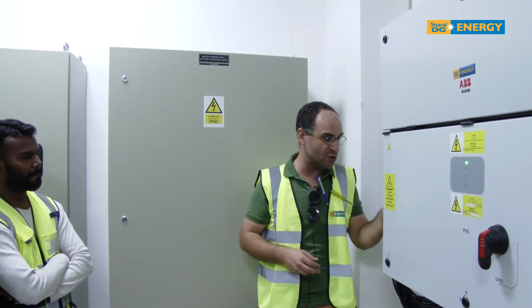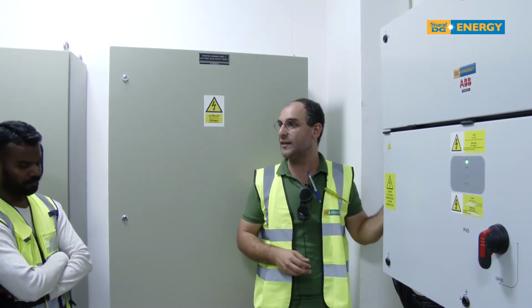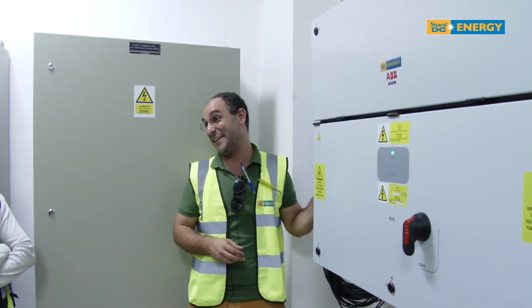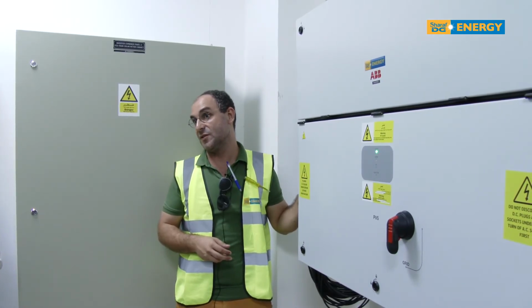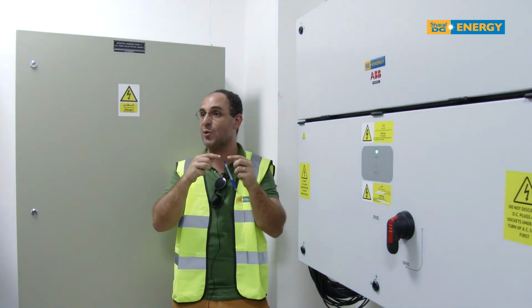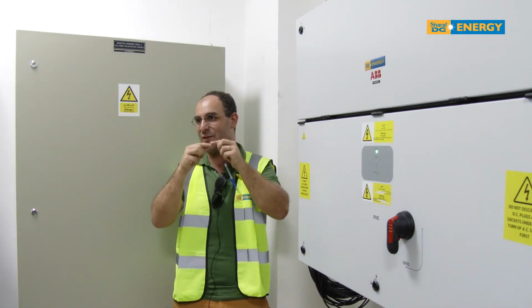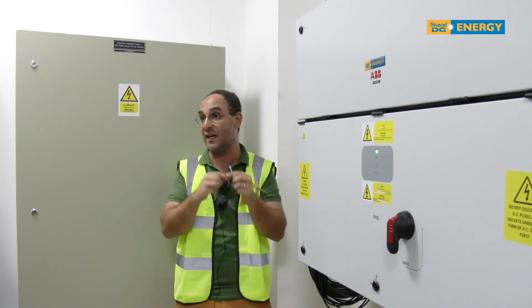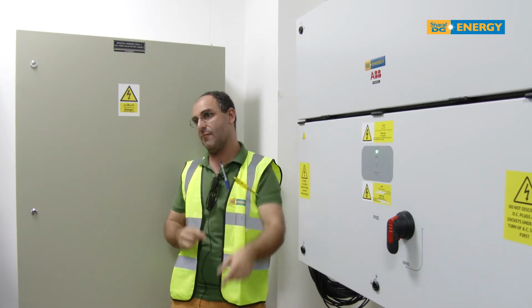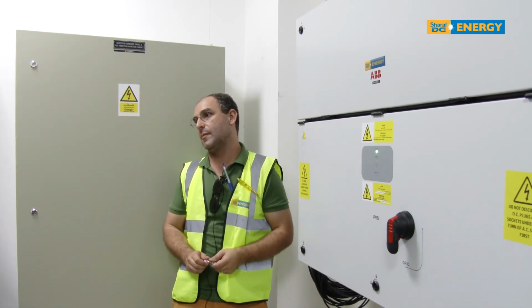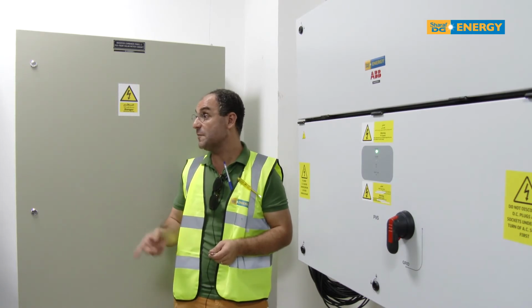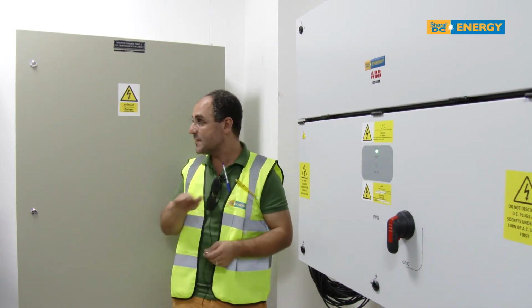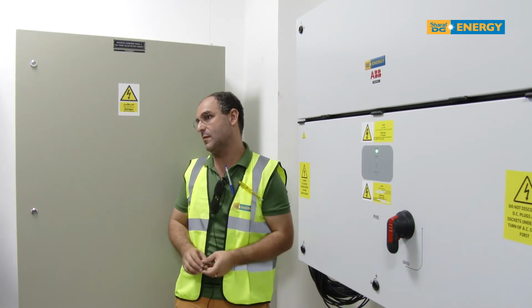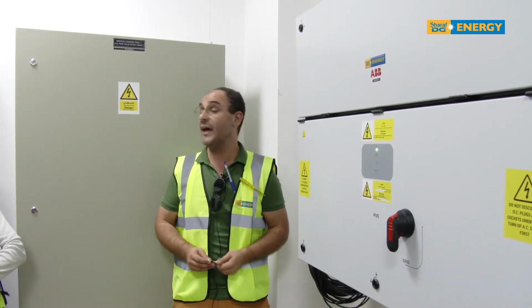So the inverter knows how many amps are coming in on the positive, and it should know how much is returning on the negative. If it is the same value, the earth leakage is okay. If there are different values beyond a certain threshold, it will indicate there is a ground fault. That's what you usually call your ELCBs. The same purpose, the same idea, but inside the machine. Okay? Any questions, guys?